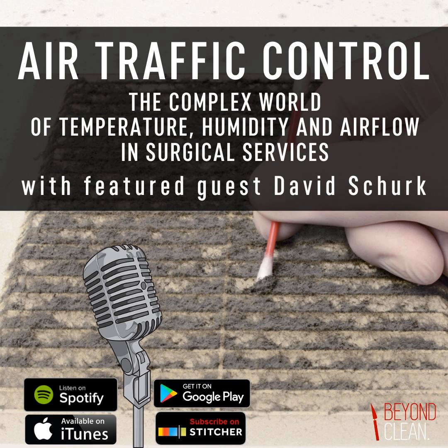So, David, with all the complexities that are involved with these systems, what are some of the most common problems that you see in the sterile processing departments when you go into hospitals? Well, probably the most prolific problems, if you will, are the ones that may not be quite noticeable when you walk in. What I mean is I think the biggest latent problem in hospital environments is just the cleanliness of the space, the cleanliness of the air, based on the type of HVAC system that is providing environmental control and what's going on within that HVAC system, as we referenced earlier, with mold growth and coil cabinets and things of that nature.